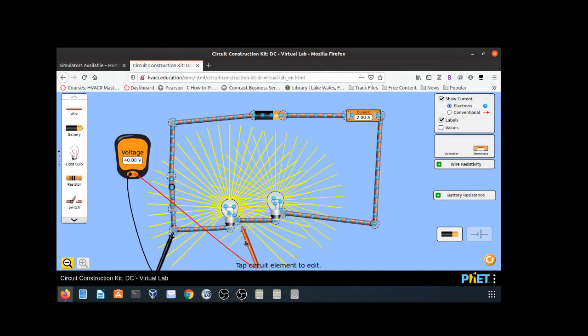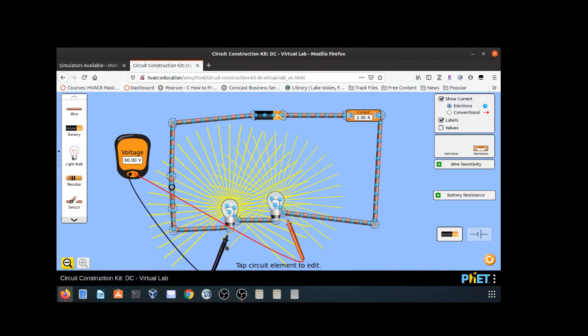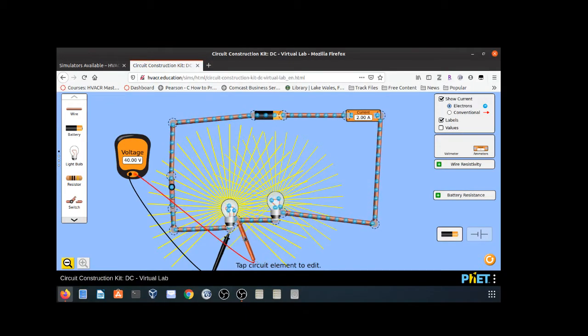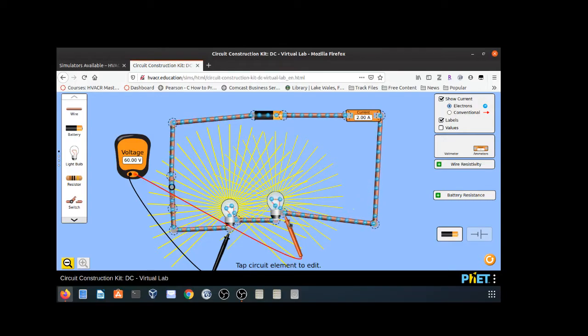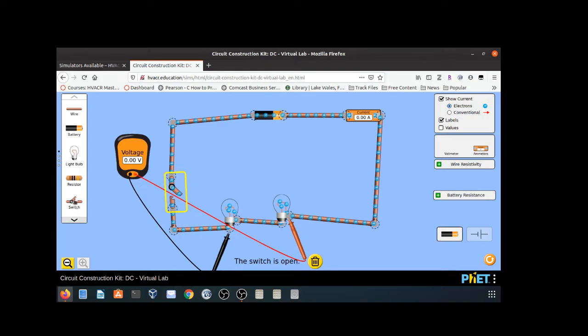My first bulb is measuring 40 volts, my second bulb is measuring 20 volts. Across the whole circuit I still have 60 volts — that's source. So all the loads in a series circuit add up to full source voltage. That's part of why we don't see many series circuits in the HVAC industry: each load only gets a portion of source voltage, and that portion is based on resistance.